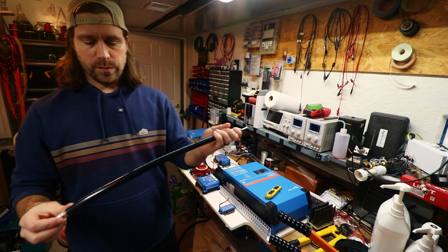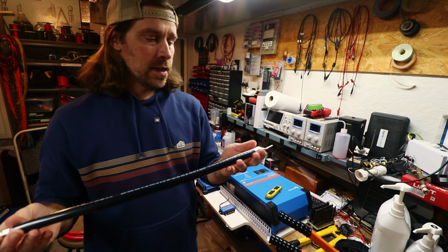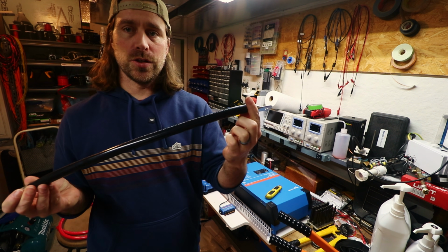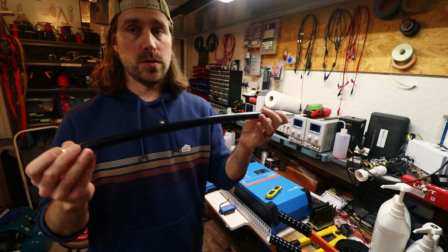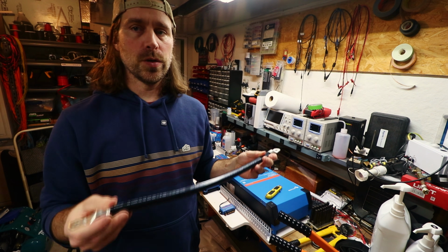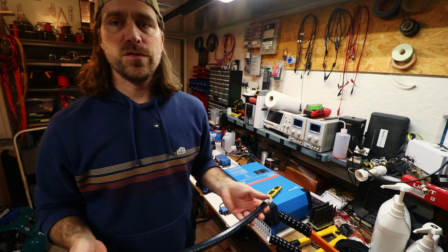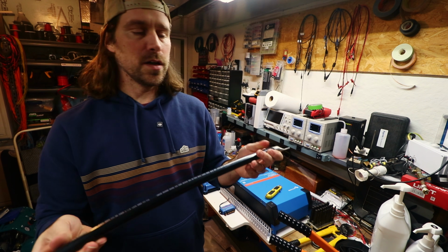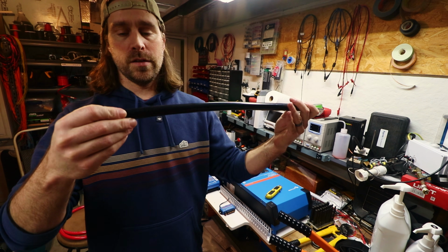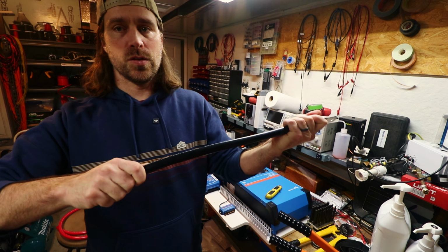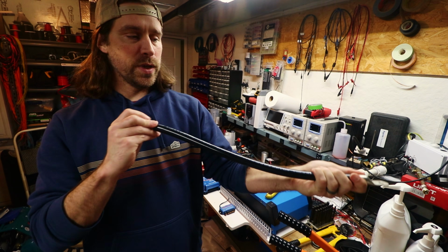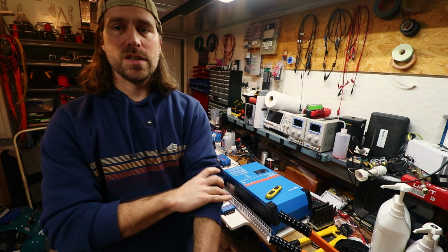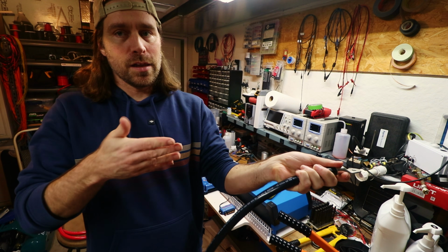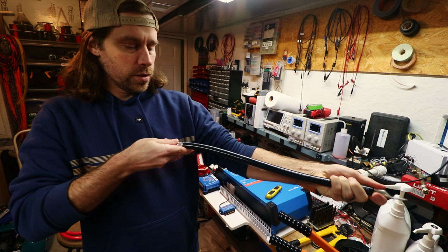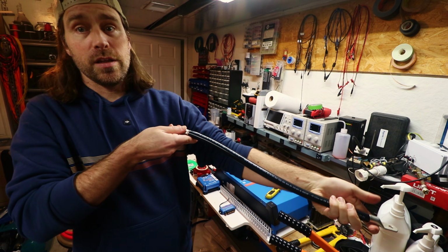One thing you definitely want to make sure of when you're crimping the second end is that you get the orientation of this terminal correct on a wire that's relatively short. If you're running a 15-foot run, it doesn't really matter, you'll get enough twist in there. But on something this big of a cable, it's really hard to get it to twist, so you really need to pay attention. It's almost like plumbing with PVC—when you glue it together, you've got to kind of clock everything. So again, just make sure your terminals are aligned the way you need them to be.